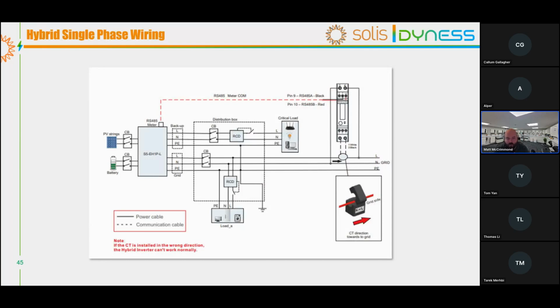Just a quick example of what we see in the manual for our wiring side. Ultimately, we have an RS485 connection between the inverter and the meter, and the meter can be installed at the grid point. When we talk about meter position, we always want it as close to the grid point as possible, and you should not touch the CT by extending or cutting the CT cable to the meter. If you do that, you can have inaccuracies on the meter. So it's always important to leave the CT cable untouched and extend the RS485 side instead. We'll show you the pins that you use in the inverter, how you get power to the inverter, plus where you plug in your CT.